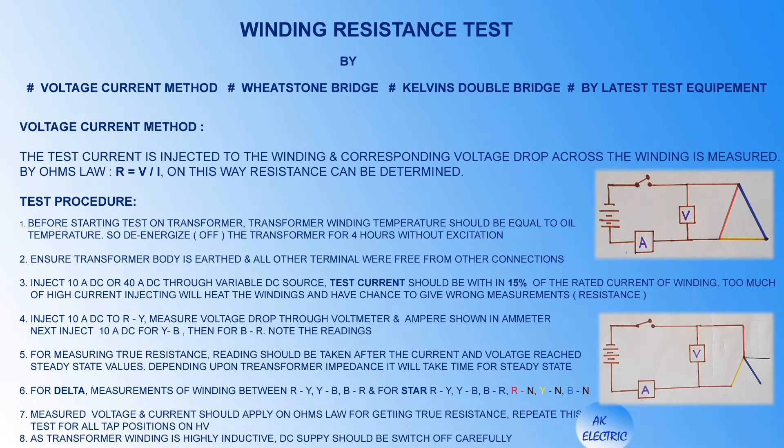Winding resistance test by voltage-current method: the test current is injected to the windings and the corresponding voltage drop across the winding is measured. By Ohm's law, R equals V divided by I — on this way resistance can be determined.